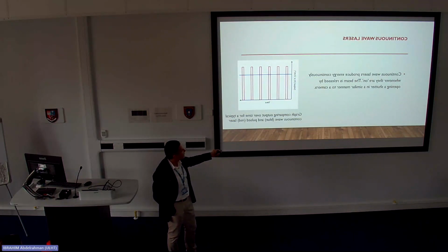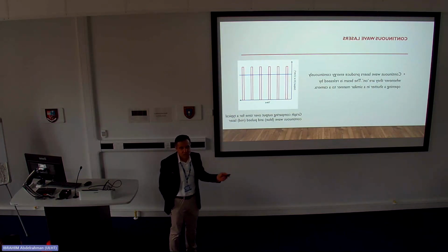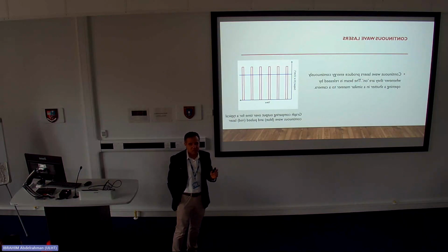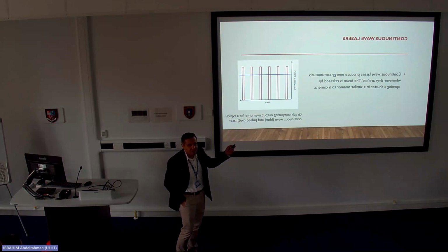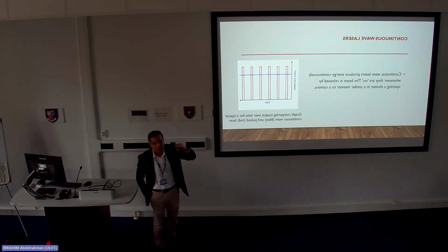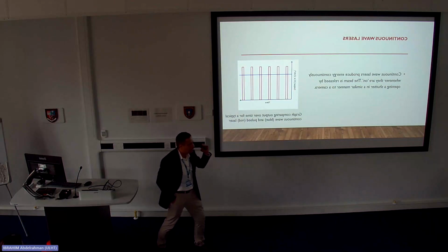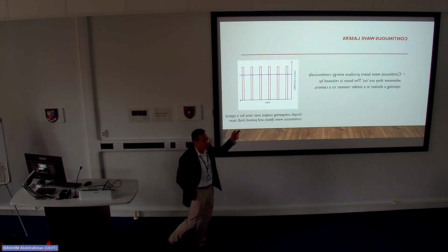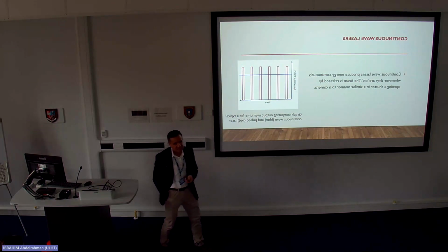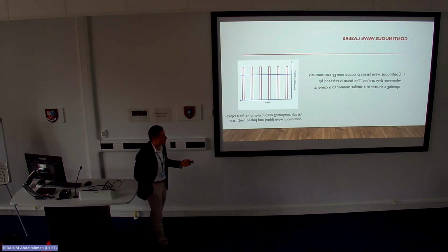Pulse means the laser goes up and down, and there's an inertia between them, so there is a loss of power. When you set it on 10, it will reach 10 in a fraction of a second, but still there is a bit of time to reach the level that you want. But in continuous, if you put 10 watts, that means your laser will be 10 watts continuously. There's no inertia to go up and down, depending on the tissue that you're working on.